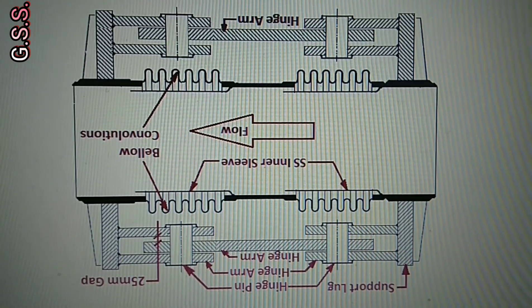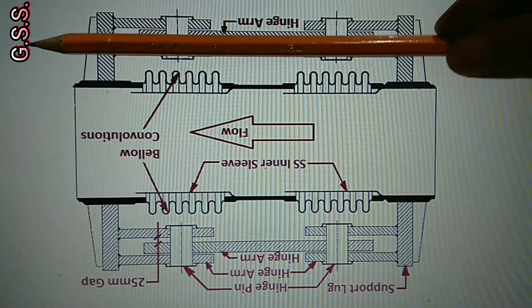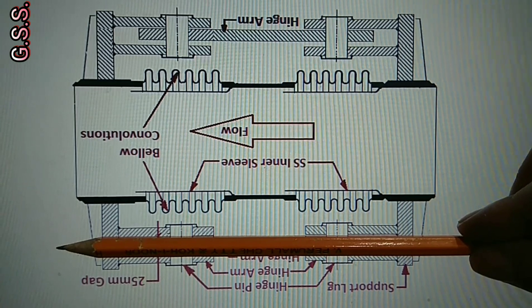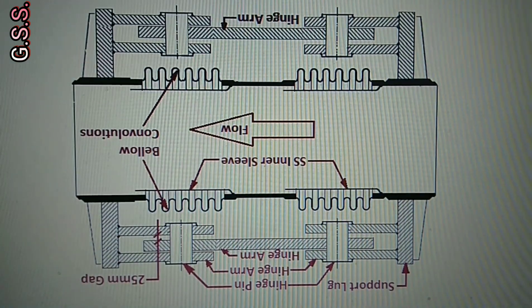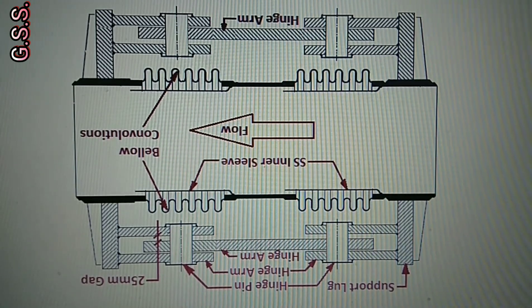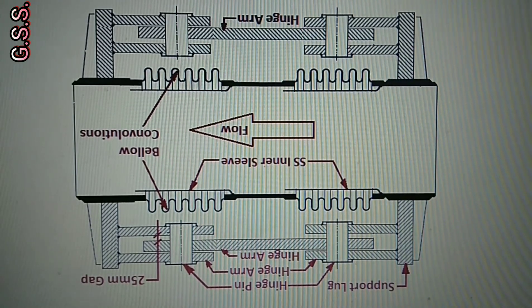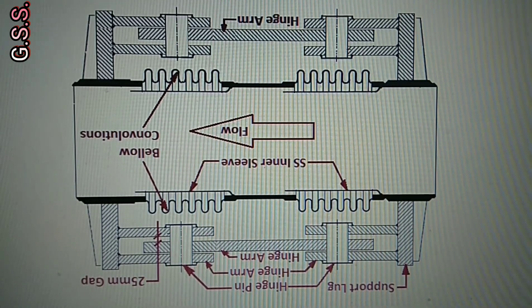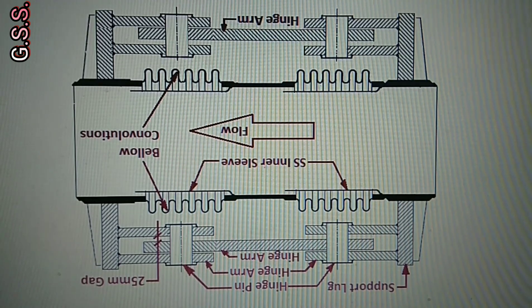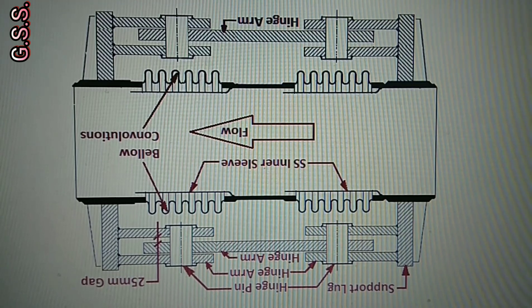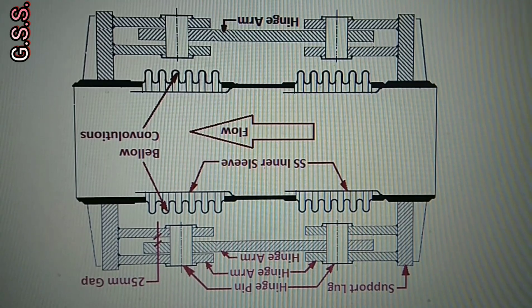If we use a tied lateral bellows with tie rod and nuts, then it will be risky because by mistake somebody may loosen tie rod nut, also tie rod nuts may not be able to take this 50000 kg load by its threading. As a result, bellows will expand axially and this load of 50000 kg will be transmitted to the piping system and to the machine which will definitely damage piping and machine.